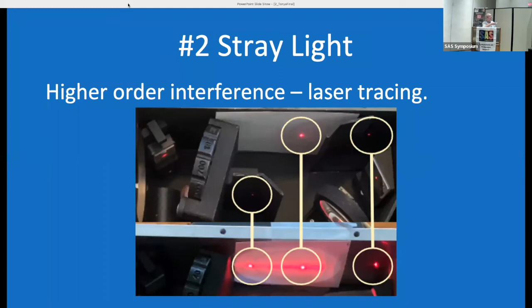Okay, this is an exploded view, an end-on view of a baffle that goes on the back of the slit, and it takes out those extra Fraunhofer lobes. These pointy out bits are baffles. Clark came along and said, let's put baffles in, let's build light traps, stop those orders going everywhere. And Jerry said, well, instead of putting them in the base of the spectrograph, let's fix them to the lid of the spectrograph. Set the spectrograph up, drop it in, job done.